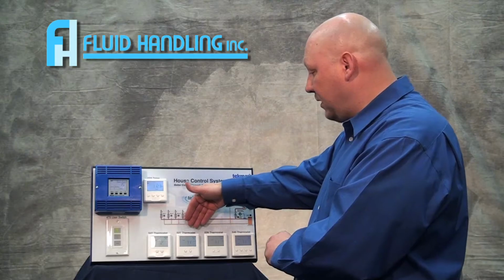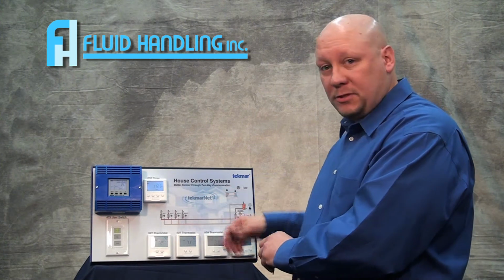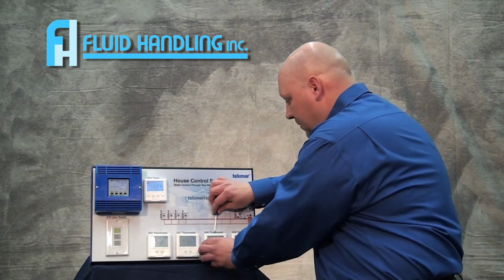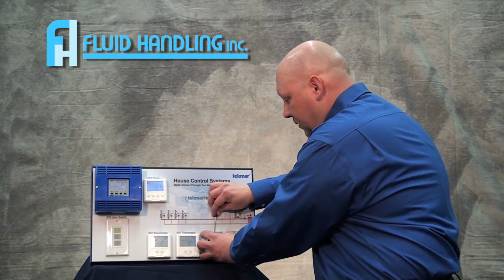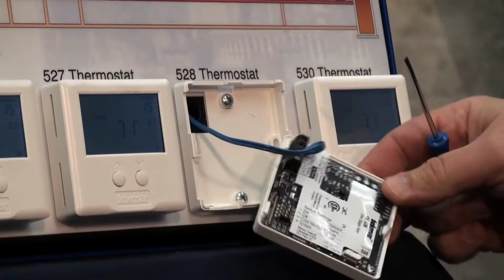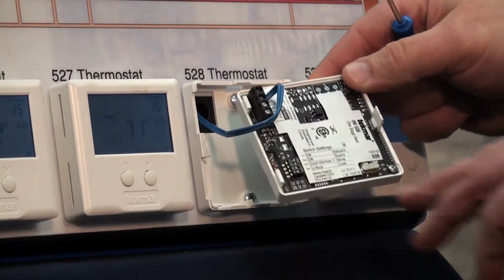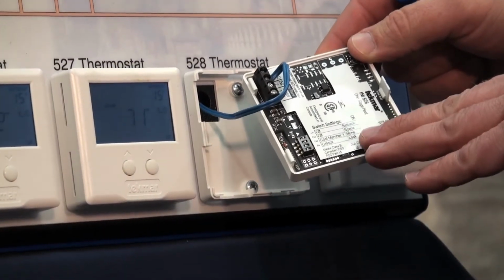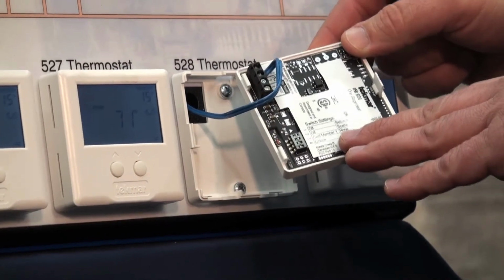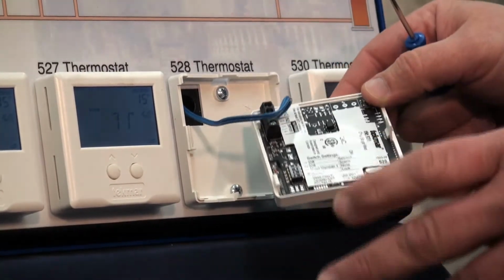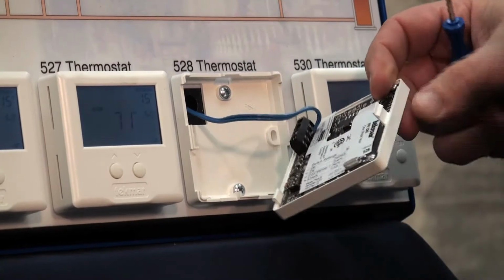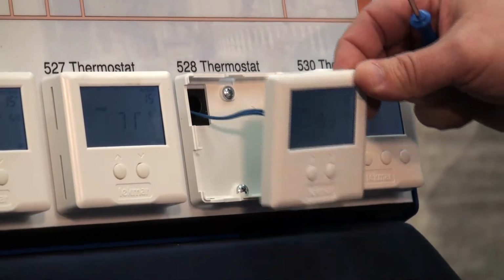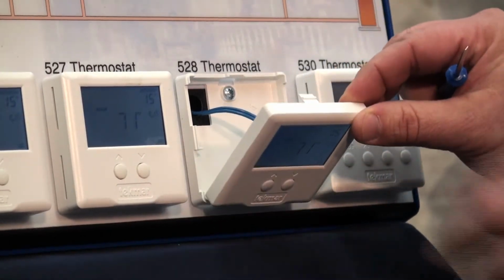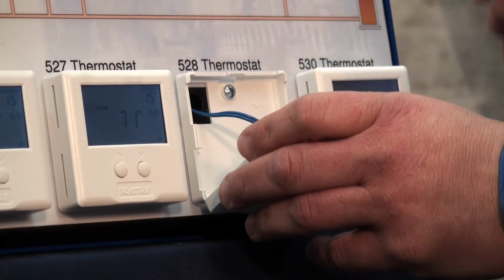So that's your 527. The 528 thermostat is the same sequence for removing it from the base, and you have your dip switches on the back again. We have the setback, the scene, if it's a cooling member, and you can actually lock or unlock this thermostat to prevent an end user from going in and getting to some of the settings. So you will need to set your dip switches accordingly.